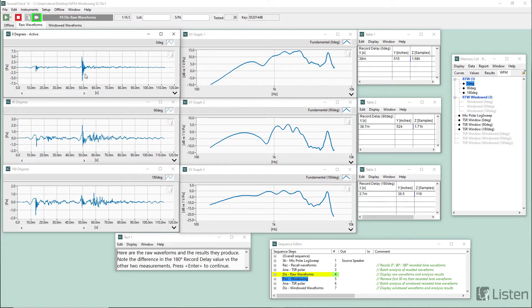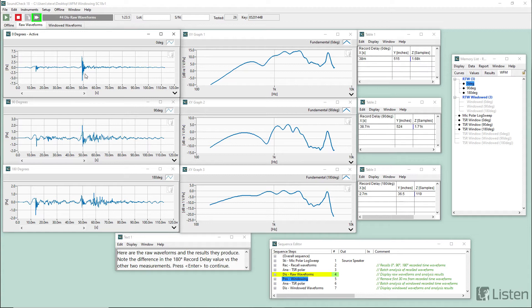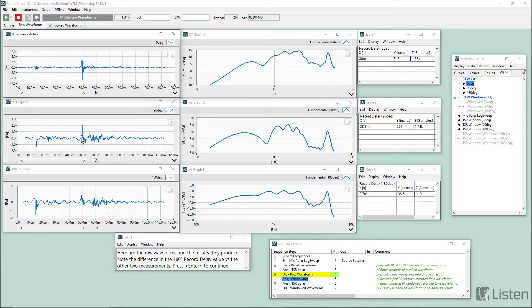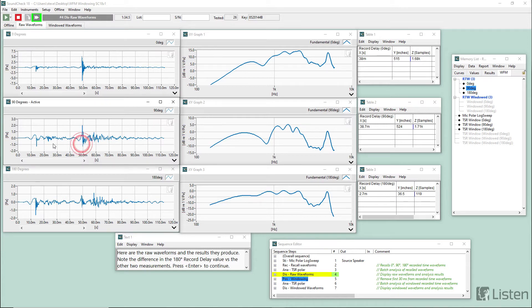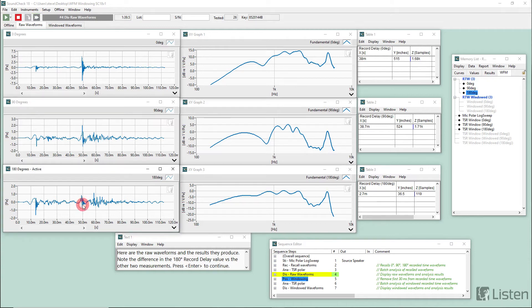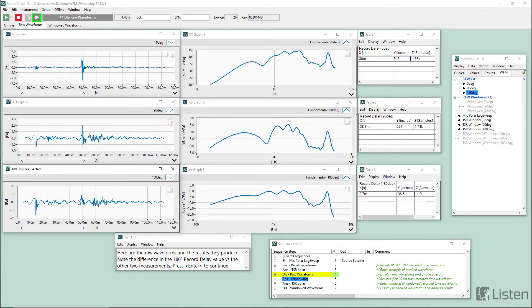And this more dominant signature down around 50 milliseconds is actually the amplified signal coming out of the device. So there's about 30 some odd milliseconds of latency during the signal processing inside of the device. And we can see that as the device starts rotating past zero degrees, the magnitude of the amplified sound starts to decrease relative to the leakage. And so by the time we get out to 180 degrees, the leakage magnitude is actually greater than the amplified magnitude.